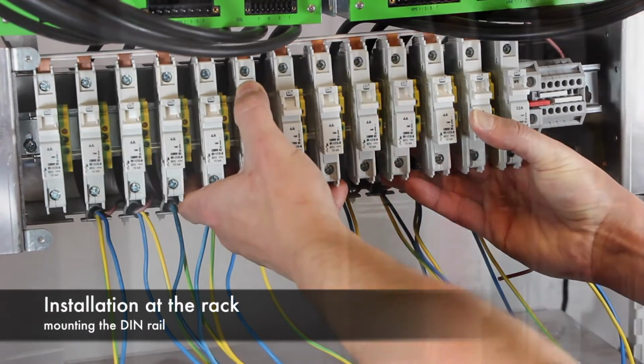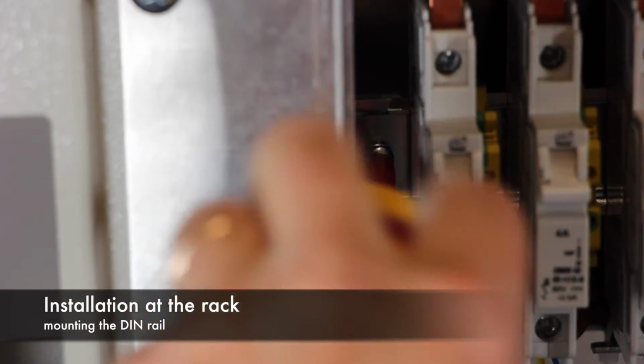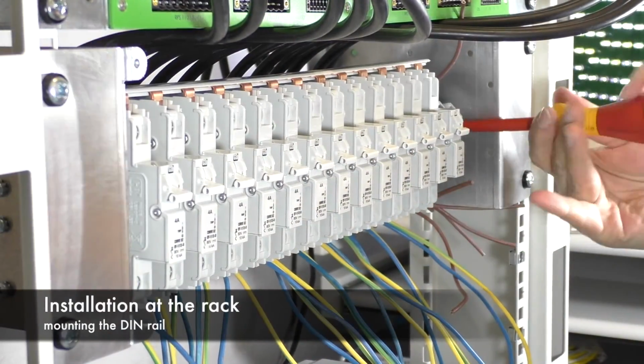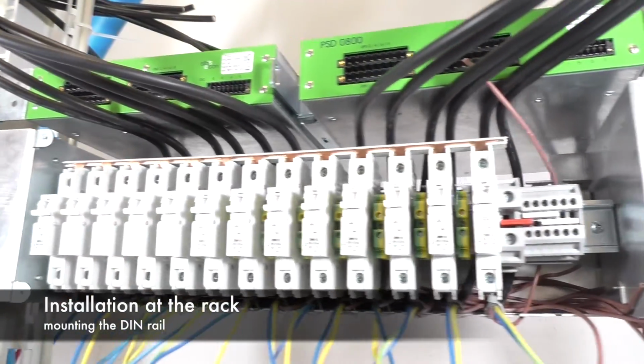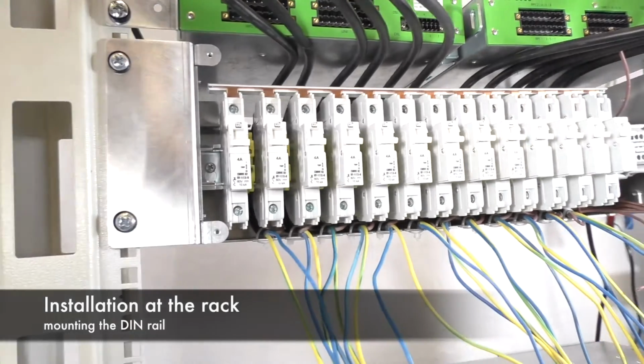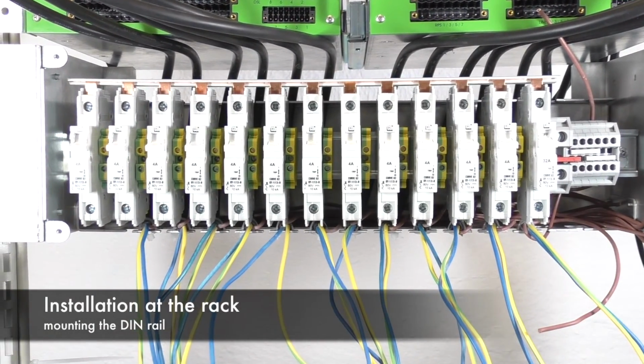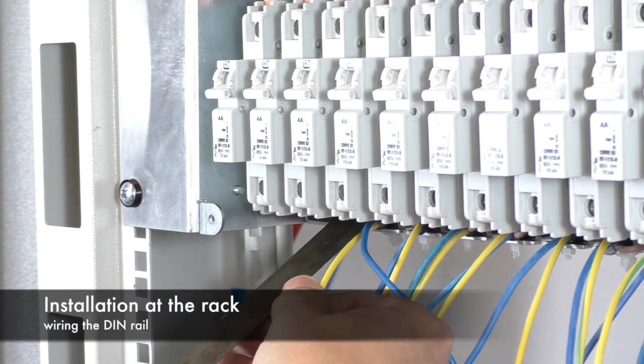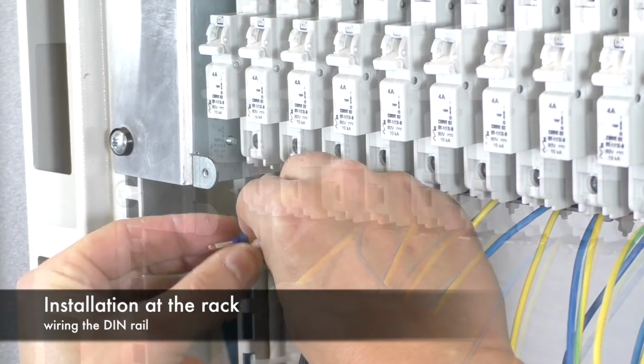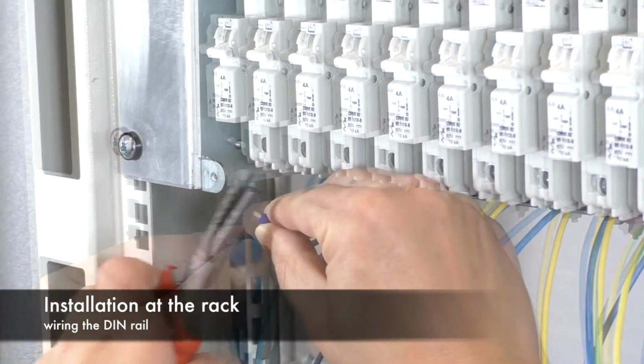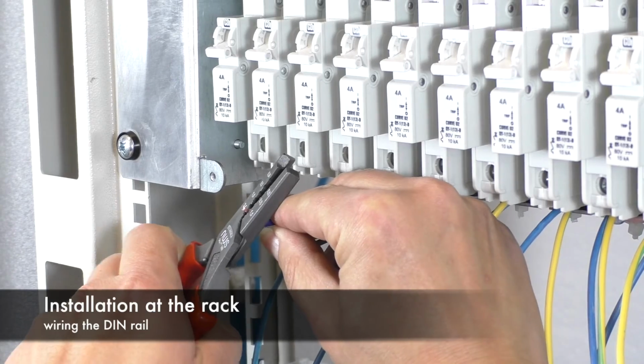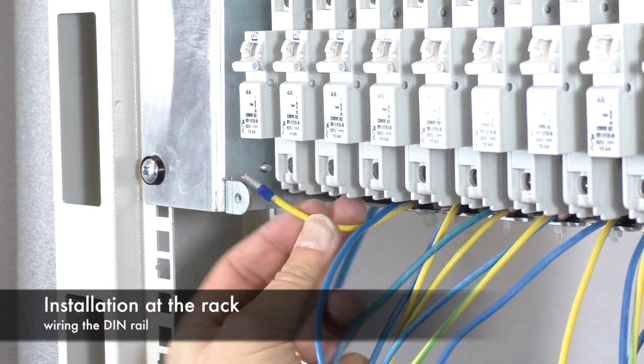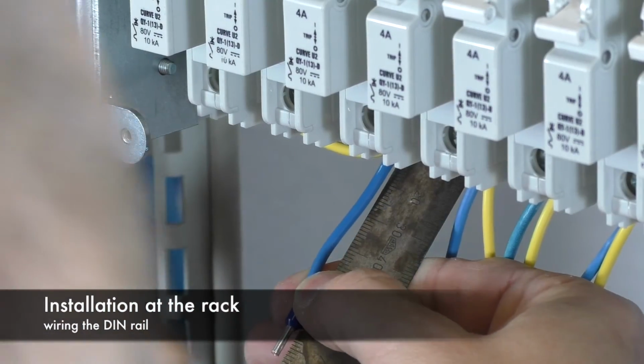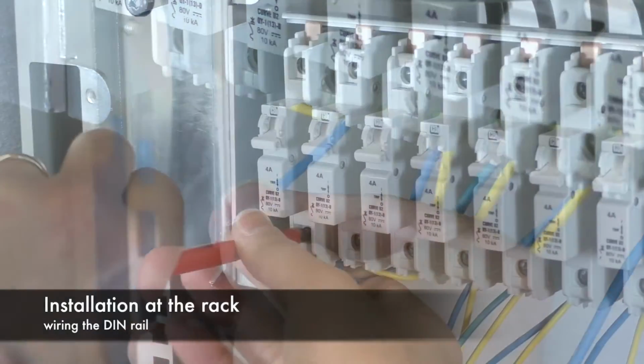You are ready to hang up the pre-assembled DIN rail. Lock the screws on both sides. Don't forget to use the washers. Before we connect the power cables, we have to shorten them to the appropriate length. Measure the distance from the lower leg of the cable guide. Shorten the yellow-green cable core to 95 mm and seal the ends with ferrules. The blue cable cores are shortened to 75 mm and sealed at the ends with ferrules as well.